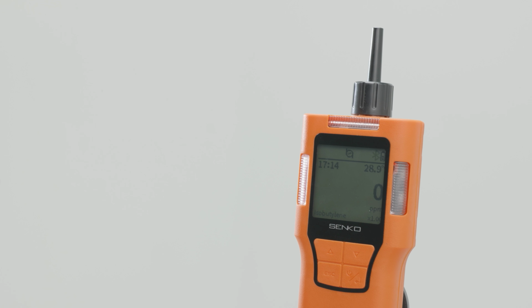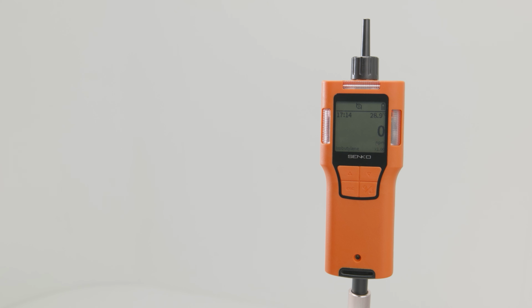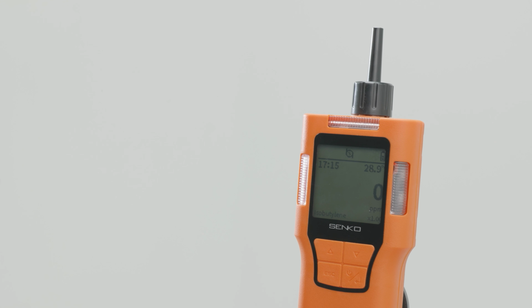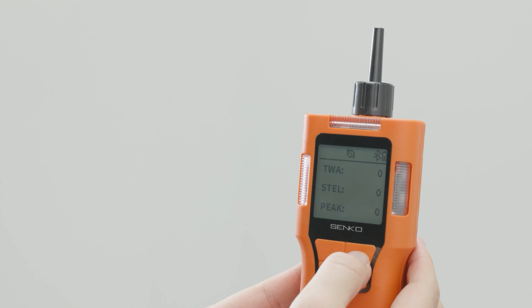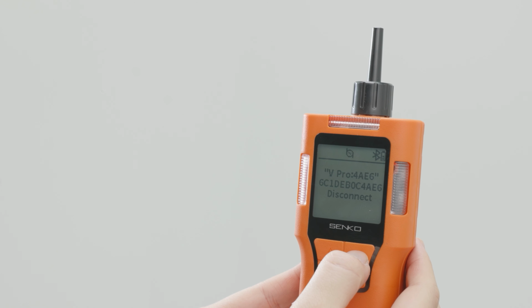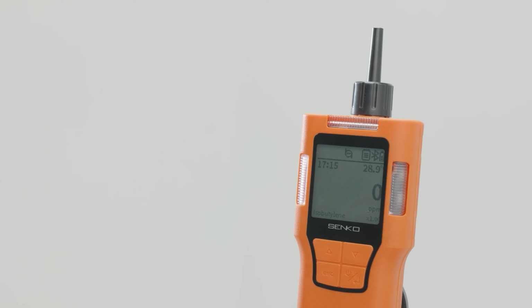After turning on the power, when the device stabilizes and switches to normal measurement mode, the current gas concentration and remaining battery level are displayed on the LCD screen. The gas concentration value is displayed in real time in ppm or ppb units, and the measured value is updated in real time according to changes in the surrounding environment. If gas concentration exceeds the low, high TWA or STEL criteria, the corresponding alarm icon is displayed on the screen, and the buzzer, LED, and vibration alarm operate simultaneously to immediately notify the hazard status. When you move to a safe location and gas concentration returns to the normal range, the alarm is automatically released. However, the alarm icon on the screen remains, and when the user presses the Enter button, the icon is deleted.